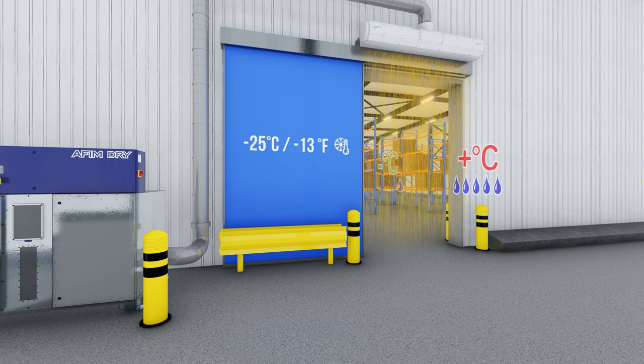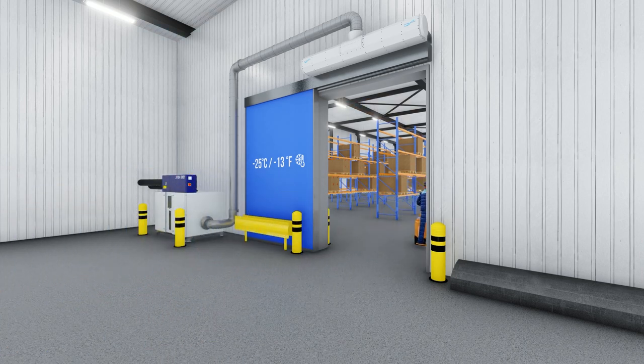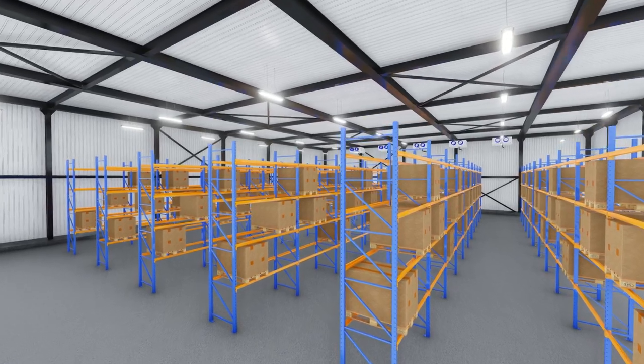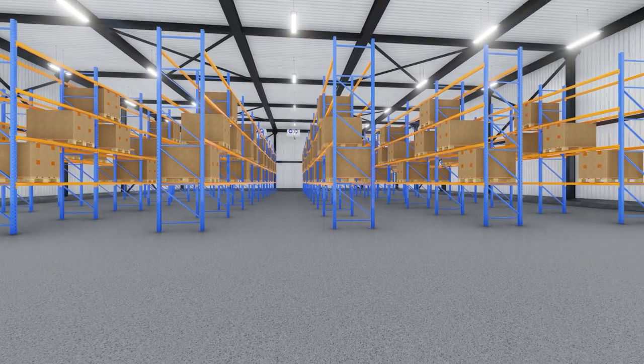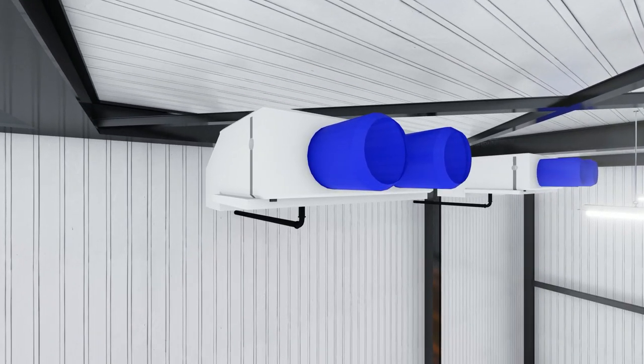This solution makes annoying strip curtains superfluous and avoids fog and visual barriers in the passage. A dry floor ensures a trouble-free logistical flow without damage and dangerous situations. With the right humidity, powders and granules will not stick. The cold store remains snow and ice-free. Evaporators maintain their optimum capacity and the number of defrosting actions is reduced, resulting in energy saving.